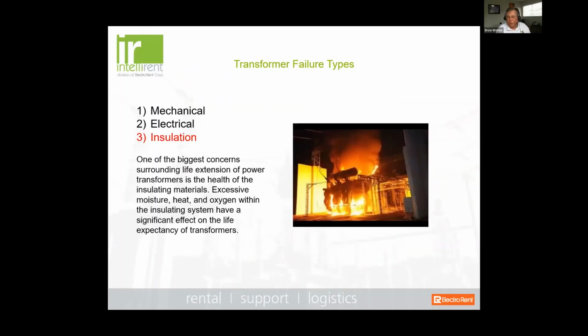Okay, let's switch gears here just real quickly and talk a little bit about insulation failures. So one of the biggest concerns that surround life extension of power transformers is the health of the insulating materials, and not just the oil, but the polymers and the paper and the windings themselves. And we know three things will cause accelerated aging, and those three things are moisture, heat, and oxygen within the insulation itself. That's a significant impact on the life expectancy.